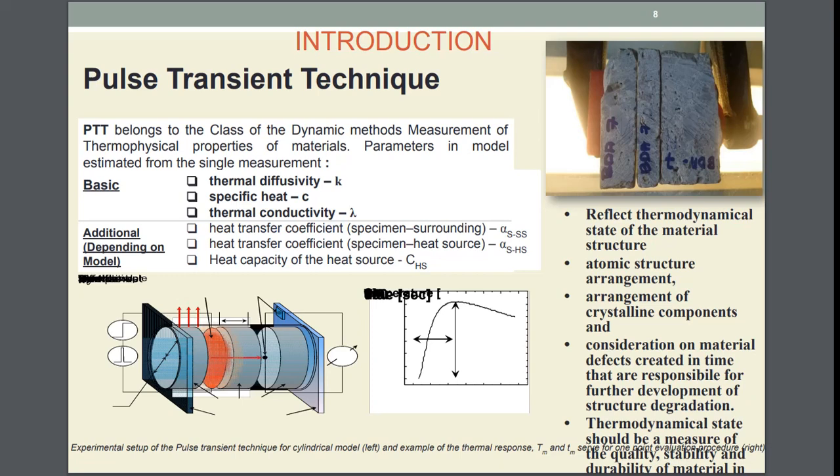And the maximum height of this temperature response is very important for us, because this will let us know the maximum of the temperature response, Tm, and small tm, at what time, and through that we can calculate and derive the formula for the maximum, which is called the 1 point evaluation procedure.